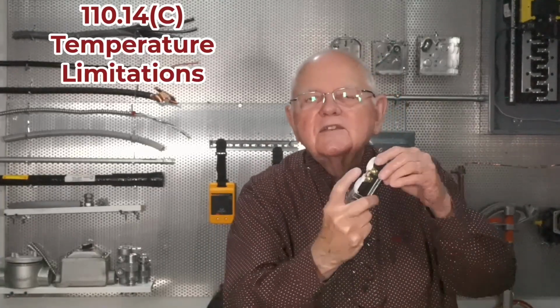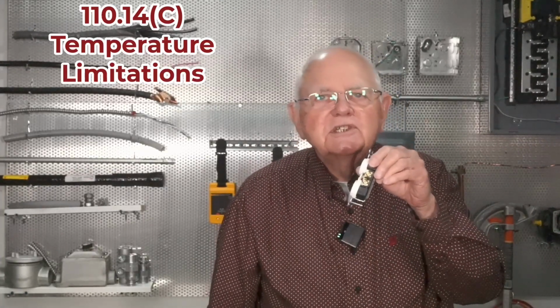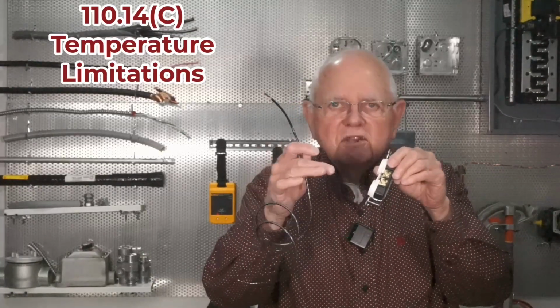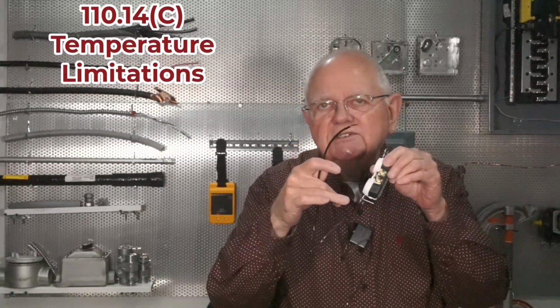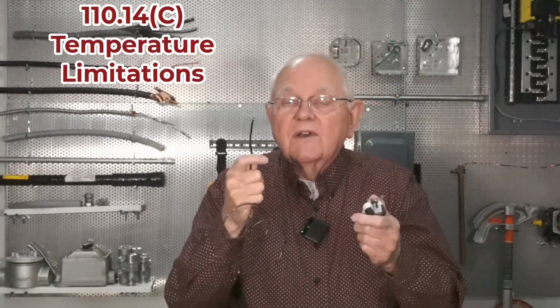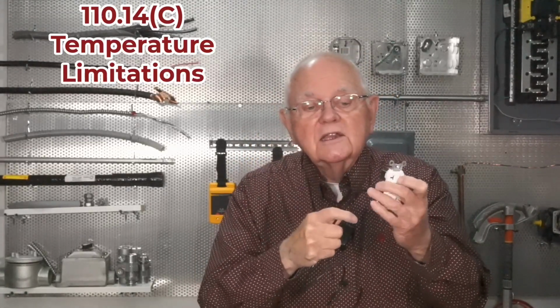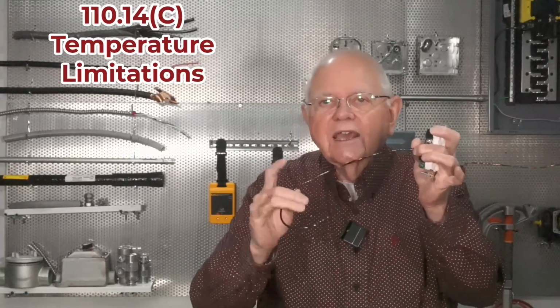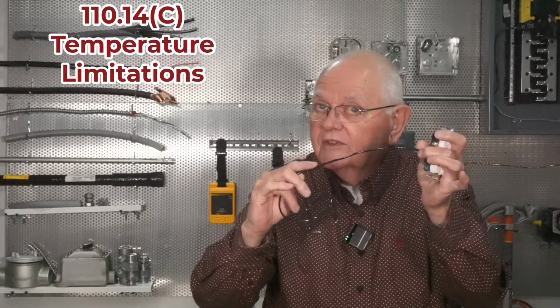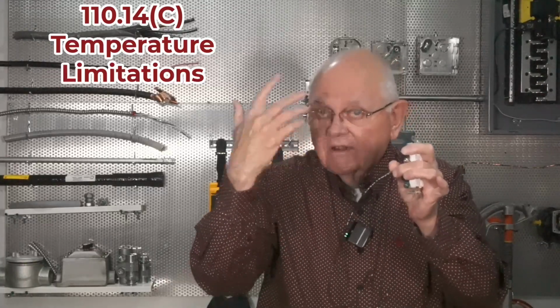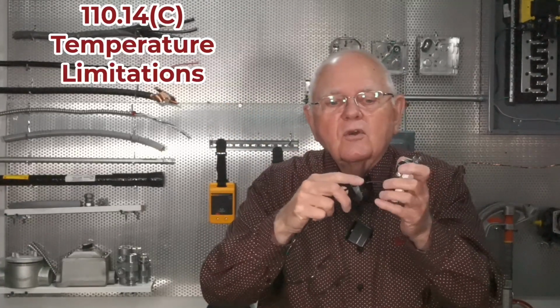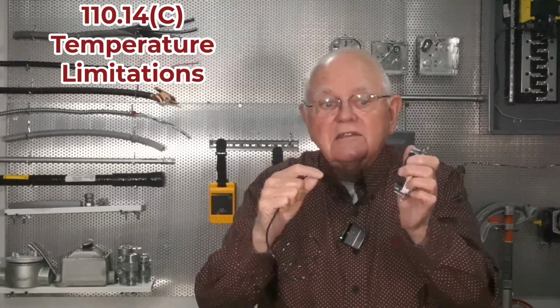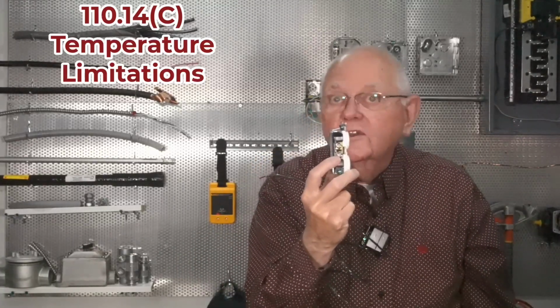Here's the problem. This wire can carry 30 amps of current flow. The terminals on this side, right? The terminals are only rated for 60 degrees C, not 90 degrees C like the THHN insulation is. So I have a problem. If I attach this number 12 wire to these 60 degrees C terminals and allow 30 amps of current flow through this number 12 THHN, at its rated ambient temperature and conditions of use, it will reach 90 degrees C. However, my terminals are limited. They're only good for 60 degrees C.